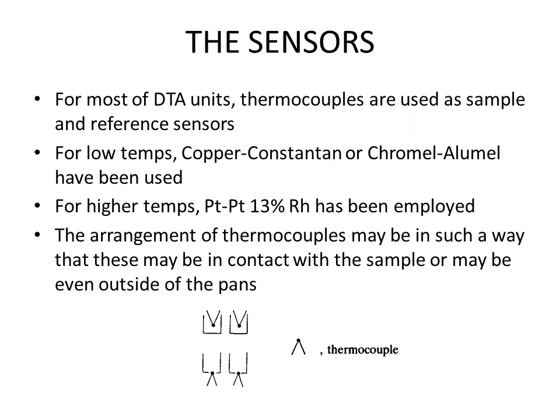For most DTA units, thermocouples are used as temperature sensors for both sample and reference cells. If working at low temperatures, thermocouples may be copper-constantan or chromel-alumel, while for high temperatures, platinum / platinum-13% rhodium can be used. There might be different arrangements for thermocouples — in some arrangements the thermocouples are in contact with the sample, while in others they are outside the pans and not in direct contact with the samples.